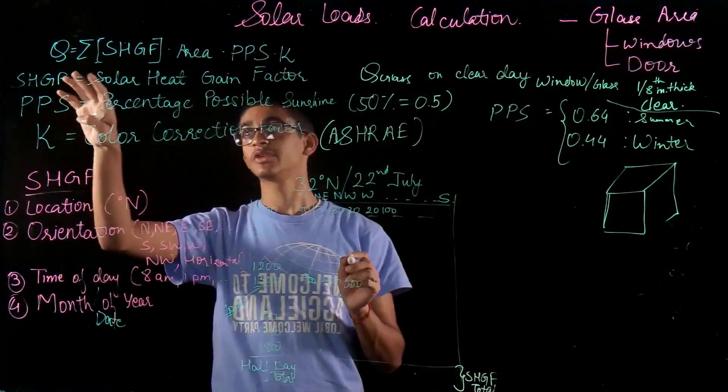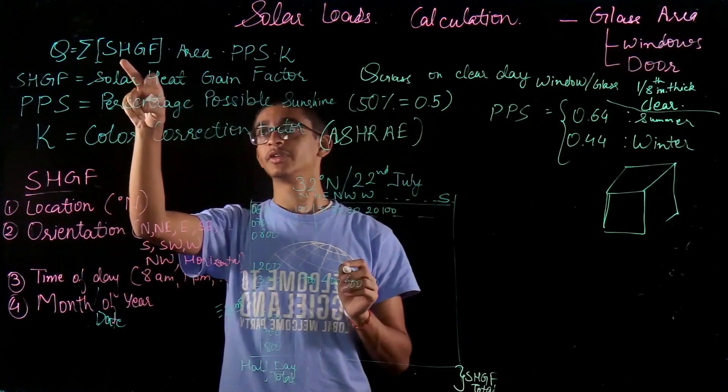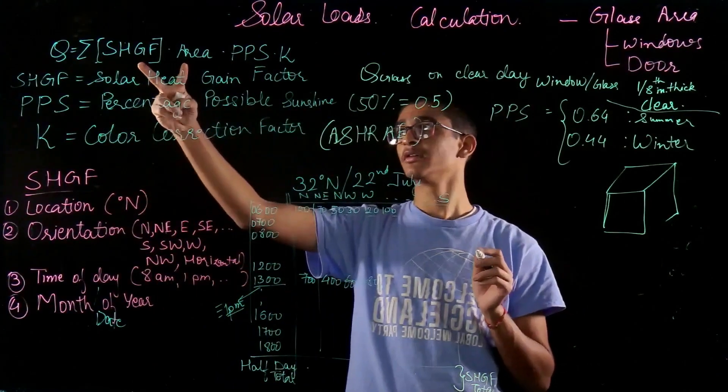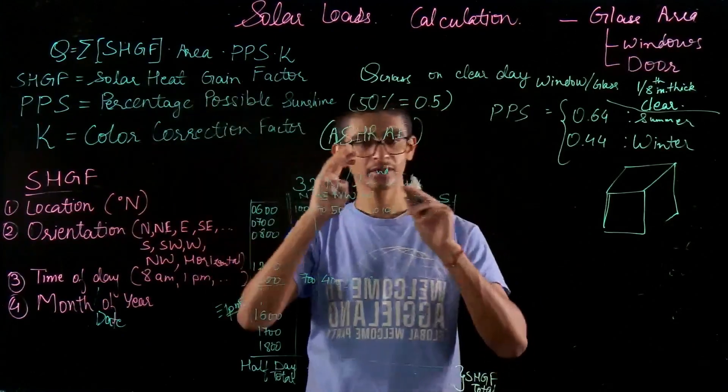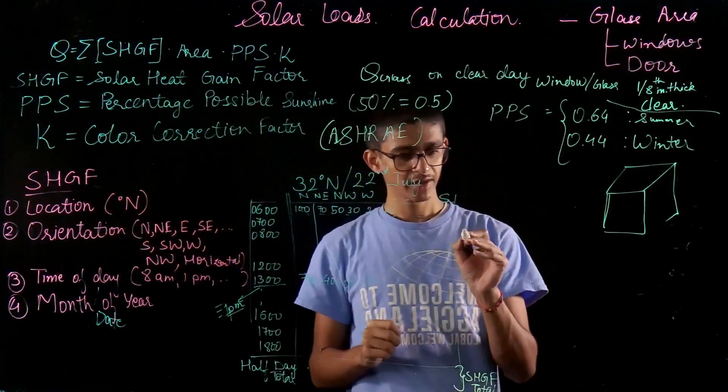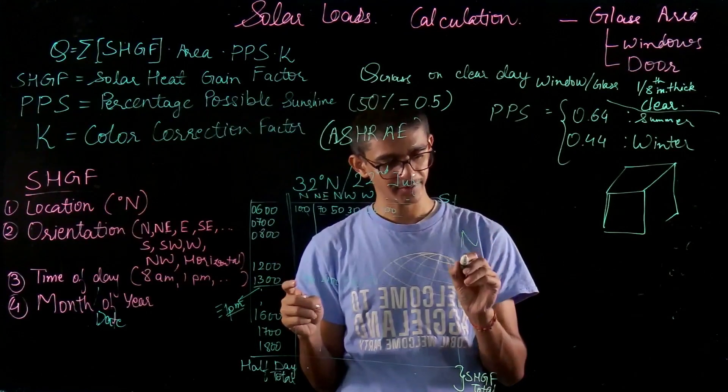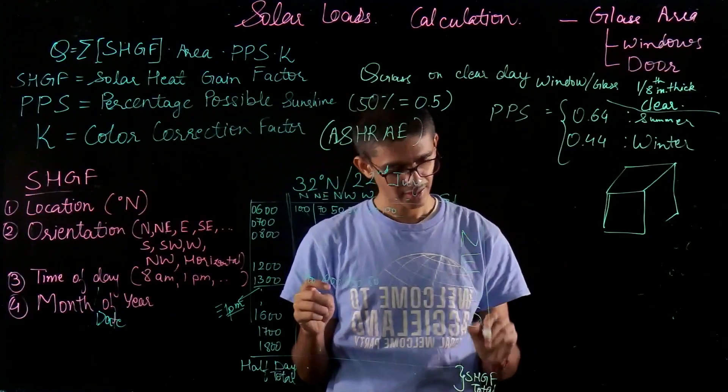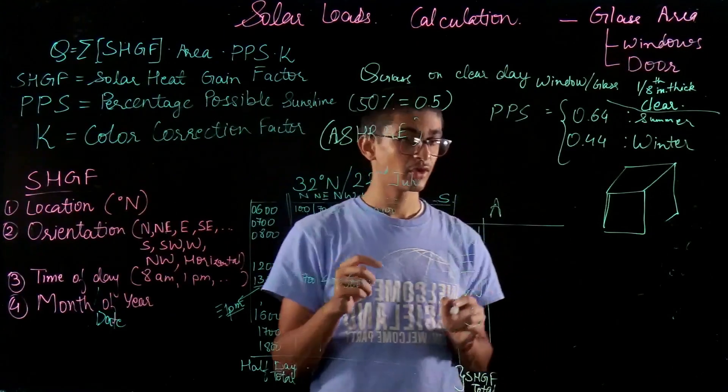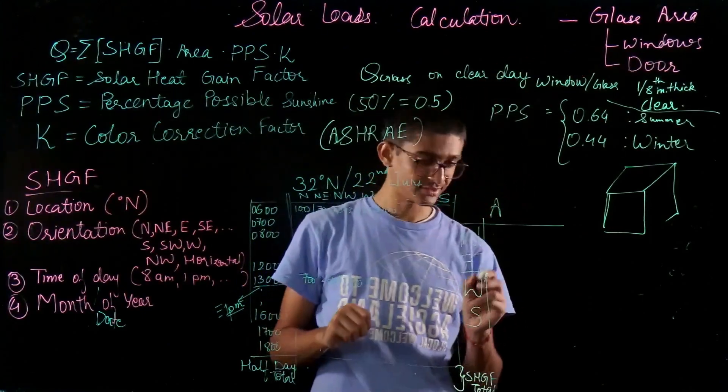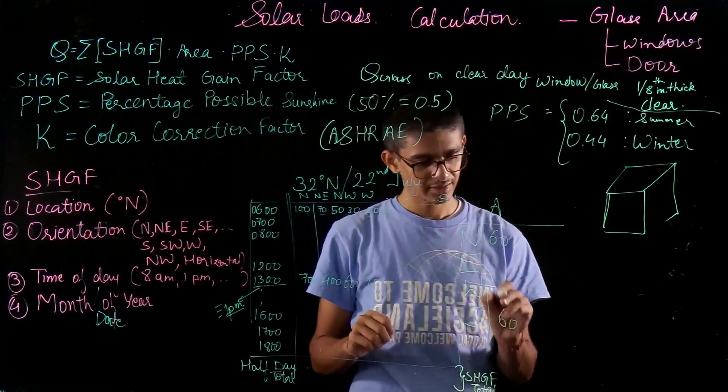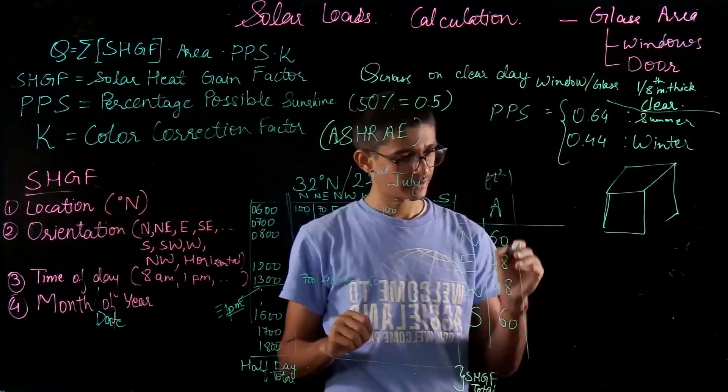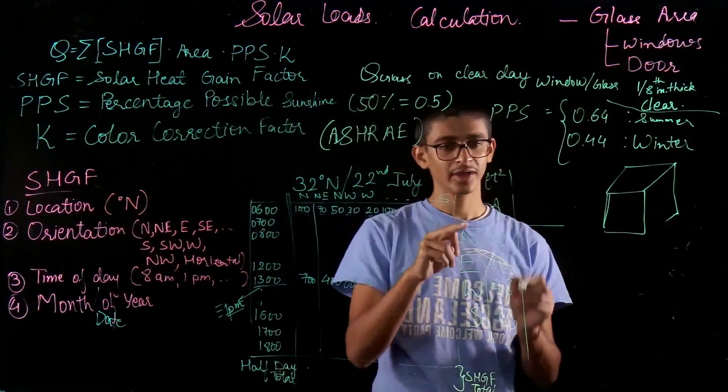To calculate the Q value, we need SHGF into area into PPS into K. PPS and K values are going to be constant, they don't change with different orientations. The areas could be changed. We need to find out the total value of SHGF into area for the building. We have four orientations: north, east, west, and south. For these four orientations, my areas of window glass area is given as north has 60, south has 60, then another two has 48, 48, in feet square.